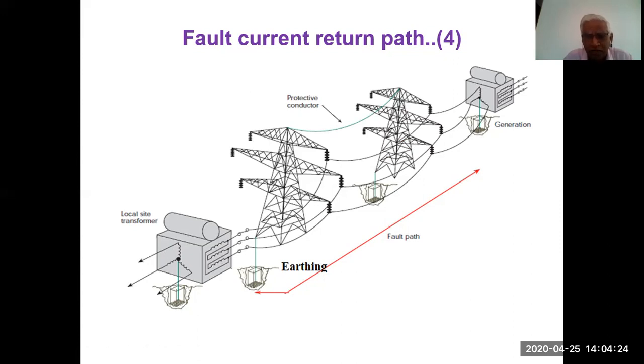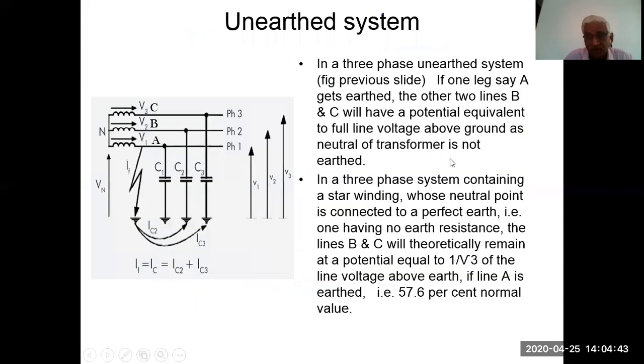So the system will trip, with an MCCB provided. In these cases it can be a bulk oil or minimum oil circuit breaker, or any other SF6 breaker or anything like that, which can open. For our simplicity, we say that a fuse is provided and the fuse will open. Now, unearthed systems. If you earth the neutral, we call it an earthed system. If you are not earthing the neutral, we call it an unearthed system. You can see here we have three phases V1, V2, V3, which I call A, B, C, and this is the neutral.